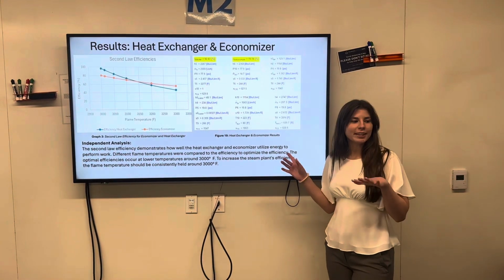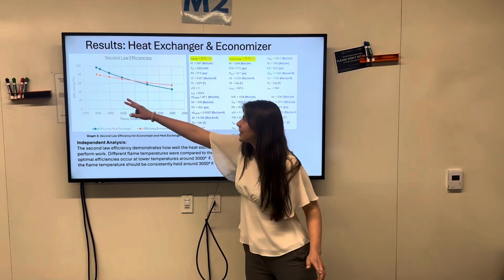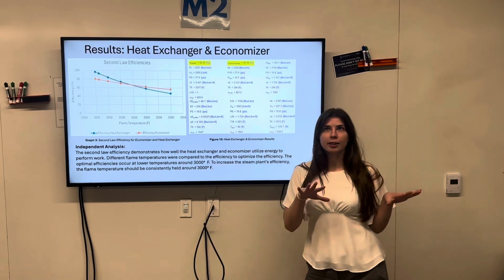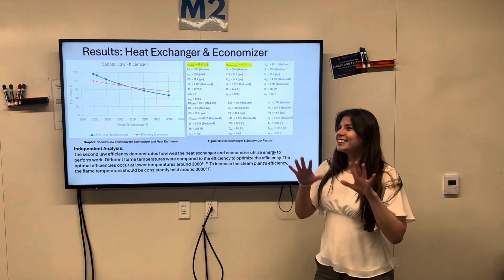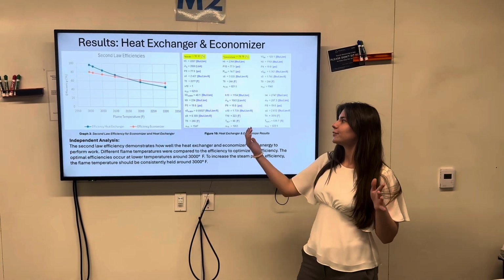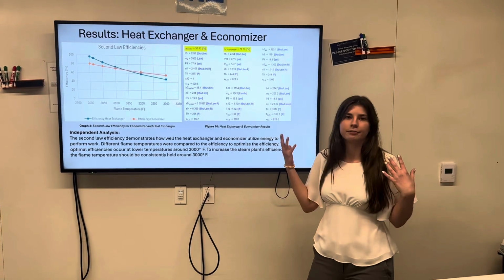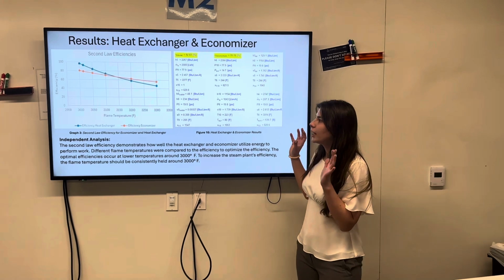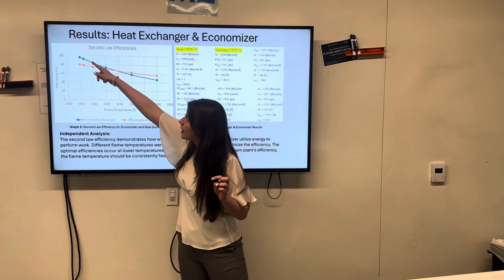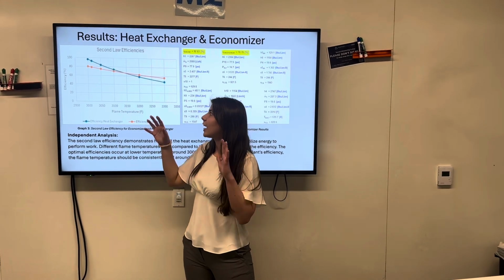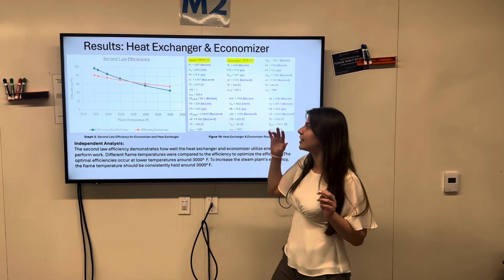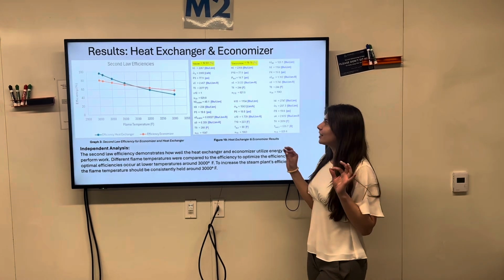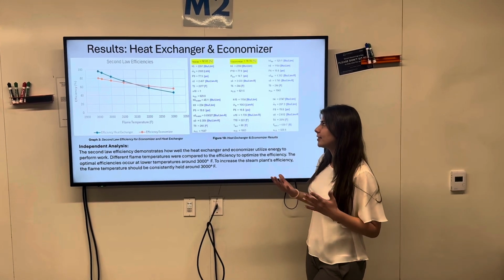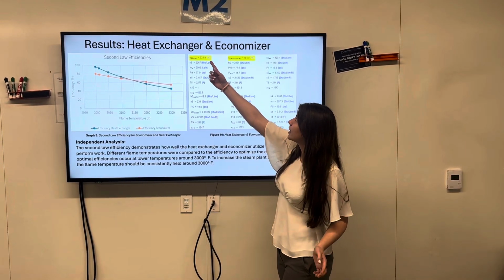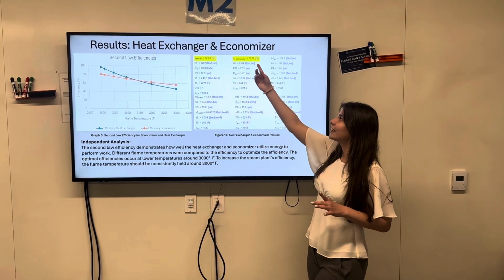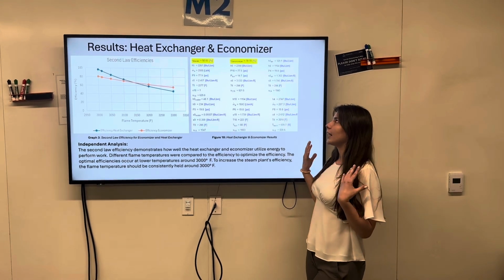All right, so then for the results for the heat exchanger and economizer, we can see that we have optimized efficiency around 2,990 degrees Fahrenheit to about 3,000, up to even 3,015 degrees Fahrenheit. And so at these values, we had a heat exchanger efficiency around 98%, and then we had the economizer efficiency around 80%. So with the actual results that we got from the data from the real steam plant, we had the efficiency of the heat exchanger to be 92%, and then the efficiency of the economizer to be 78%.